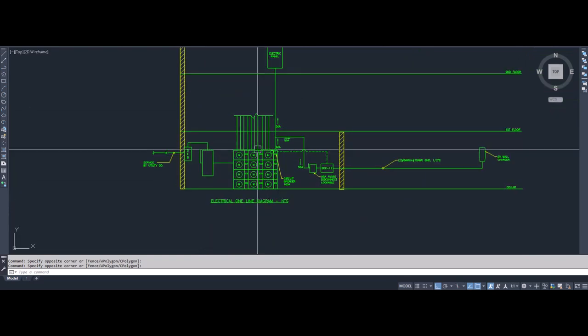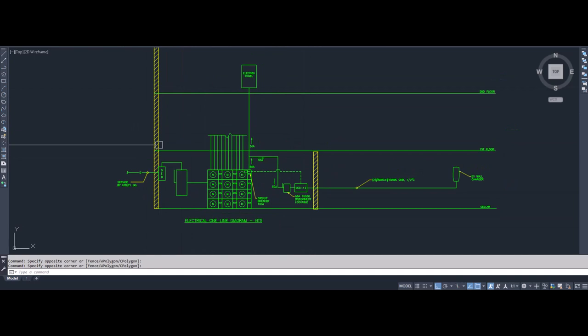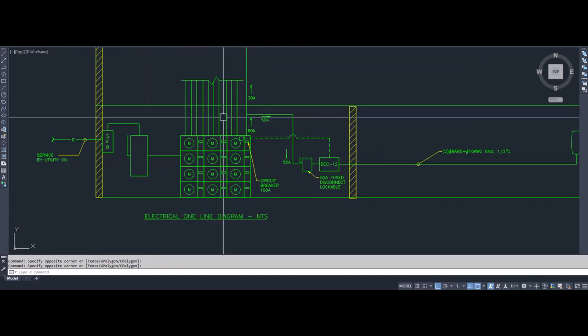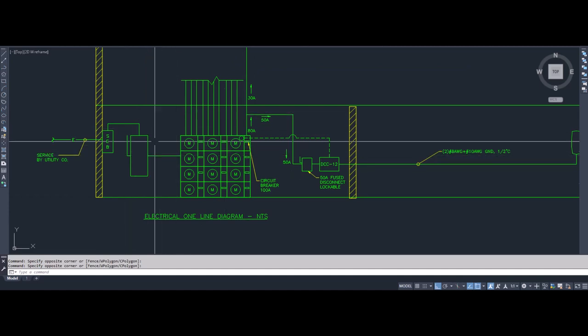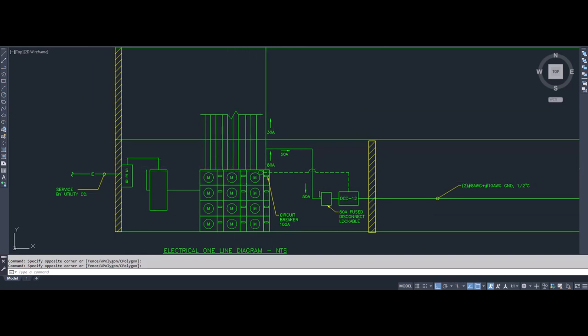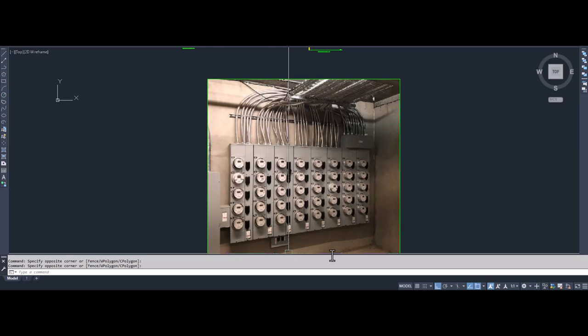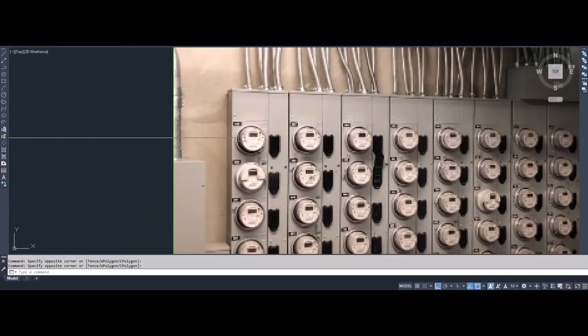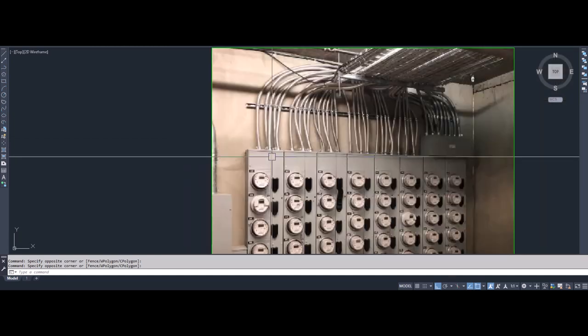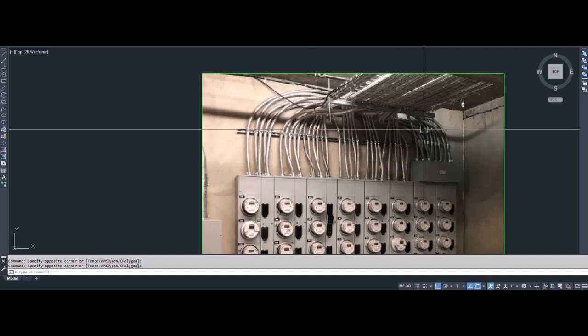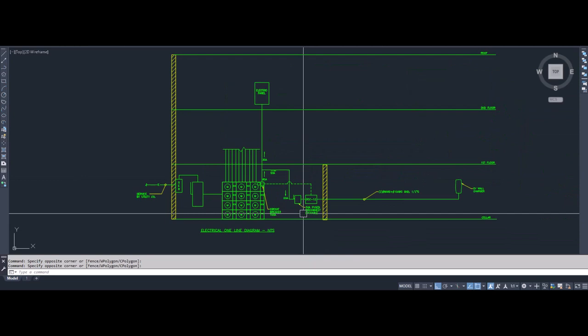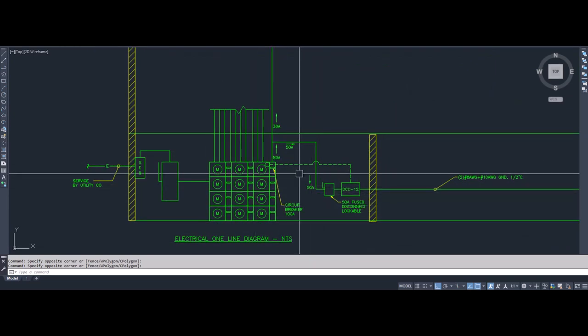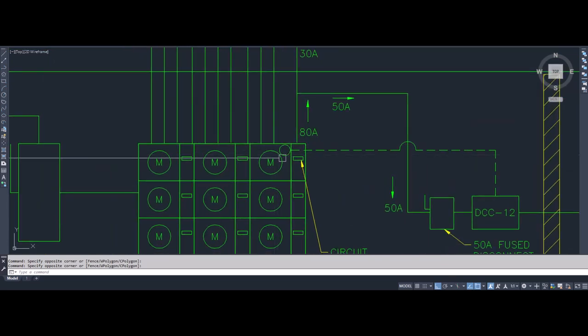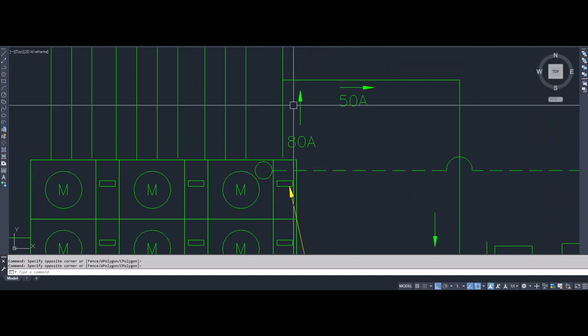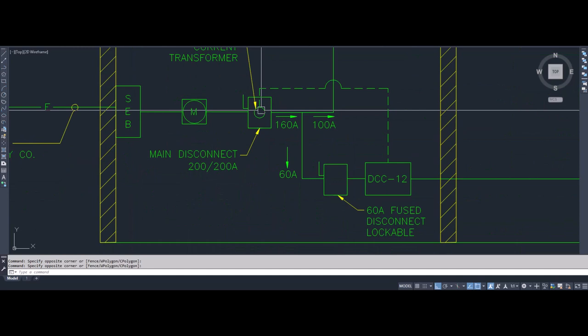The other case, you might have a system like this in a multifamily condo or co-op building where you have a meter bank. So you have one main disconnect that will send power to the meter bank, and from here it goes to the individual tenants. And a meter bank looks basically something like this. And in this example, these are the breakers for each of the meters. So you can see each meter has their own breaker that then serves the feeder to the tenant's panel. So in that case, you install it a very similar way. But in this case, the only difference is the CT is in the meter bank, basically around the feeders going to that tenant. In the previous case, the CT was in the disconnect that was going up to the tenant's panel.